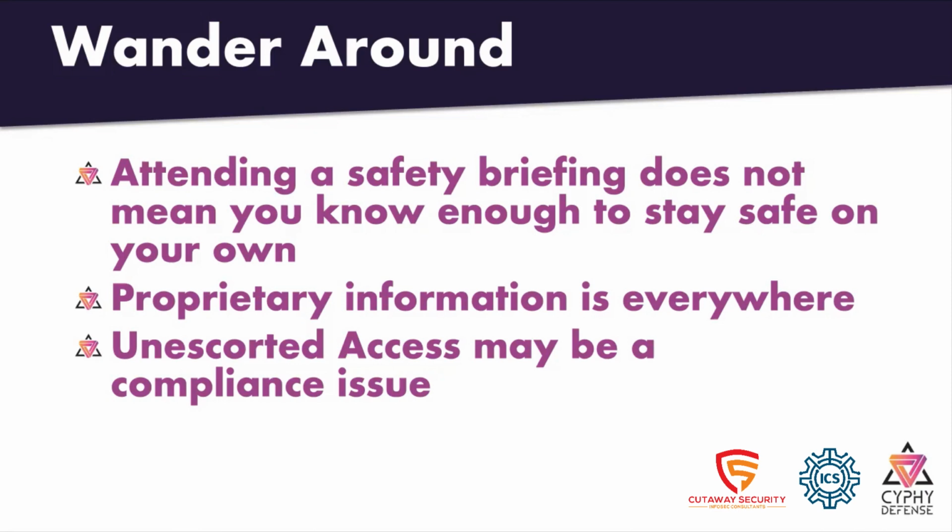In the electric world, we have what we call NERC-CIP compliance, where in general, escorted access means line of sight. So if I'm in a facility where I need escorted access because I haven't had my background check performed and all that, and I walk around 3 racks to the other side of the room where my escort cannot see me anymore, that's actually a compliance violation, which probably should be reported or may need to be reported. And if you don't report it, then there are even more compliance issues.